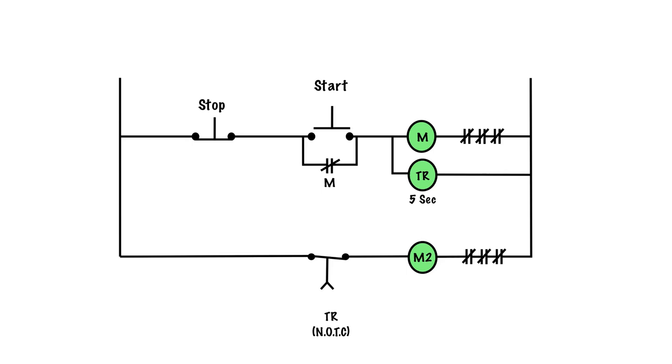So again, the sequence: press start, M energizes, contacts close, TR energizes at the same time. 5 seconds later, this counts for 5 seconds, then this set of contacts closes, and M2 starts. So M1 starts instantly, M2 starts 5 seconds later.